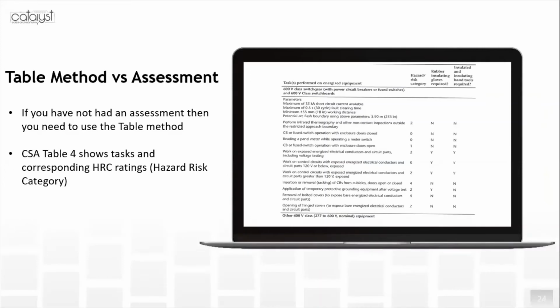Table method versus assessment. This pertains more to facilities or general contractors who have an idea of what they're going to do but don't really know. If you really don't know, you have to look at the tables in CSA Z462 — this is critical. With assessments, they go through all this and define it, and when an assessment is done on a facility, the engineer puts a sticker or stamp telling you what clothing to wear for that application. The table method gives you an idea of the work being performed and what to wear. That's for cases where you don't have an assessment done.